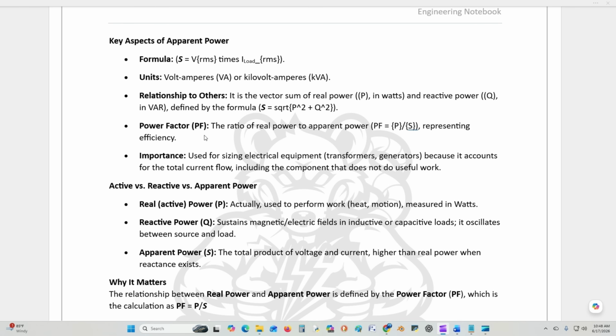The power factor is the ratio of real power to apparent power. PF equals real power divided by apparent power, and it represents efficiency. It is important for the sizing of electronic equipment, transformers, and generators, because it accounts for the total current flow, including the components that do no useful work, the inductors or the reactive components.